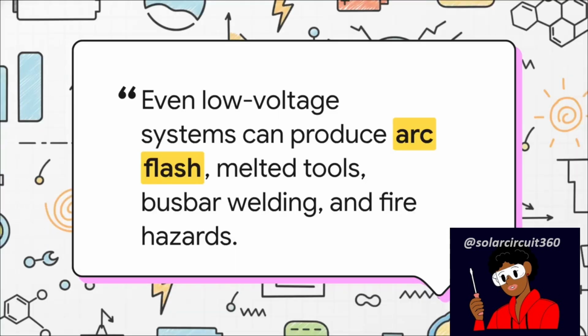Never underestimate the massive stored energy we're dealing with here. As our source material explicitly warns, even in standard 48-volt off-grid configurations, a fully charged battery contains an enormous amount of raw energy. An abrupt disconnect under high charging current isn't just bad for your equipment's lifespan, it is a highly hazardous event that can cause wild voltage spikes and dangerous arcing. It's a true worst-case scenario emergency protocol that we absolutely want to prevent at all costs.